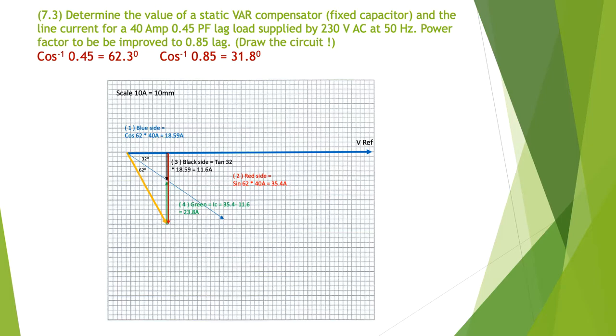I then take the green side: 35.4 minus 11.6. Basically all I'm doing is subtracting those two, giving me the green phasor of 23.8 amps.